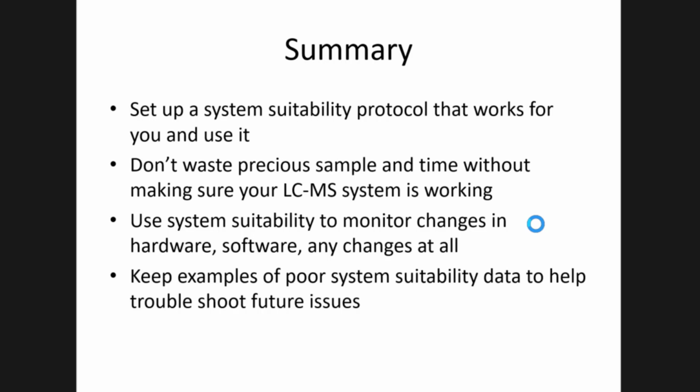If you accidentally injected air on your system because your autosampler vial was empty, you can look at the pressure trace and the lack of signal, and those things combined will help you know that you injected air. So you might not have to go through the entire troubleshooting process each time if you have common things happening to your system, whether it's dirty, the solvents aren't degassed, or you ran out of sample.